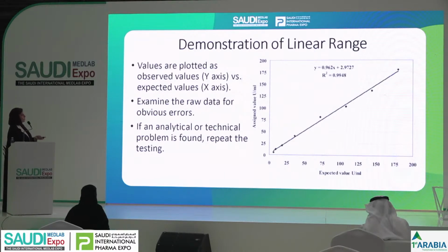So I got this, and we will go with the acceptance. This is my acceptance criteria. Some people with linearity go with total allowable error. This is okay, and this is the best one to be used for linearity, but nobody can understand it. As I mentioned, I want to make it simple for you. These are enough for linearity study as acceptable criteria.